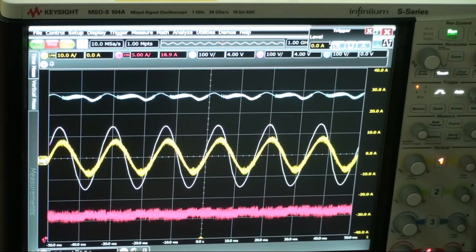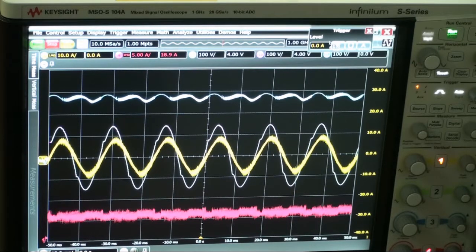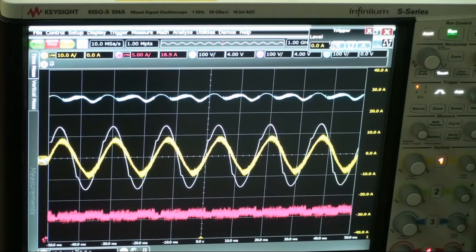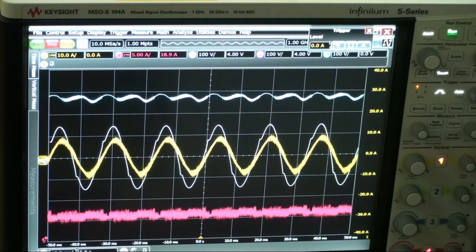At this point, the grid voltage sag has occurred, and the controller responds by injecting reactive power to the grid, which is evidenced by the grid voltage leading the injected grid current. With maximum power harvesting maintained, the reduction in grid voltage has increased the active current reference, along with the non-zero reactive current reference, leading to a notable increase in the current amplitude.